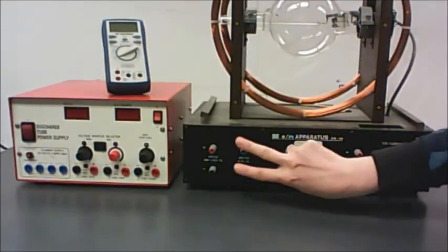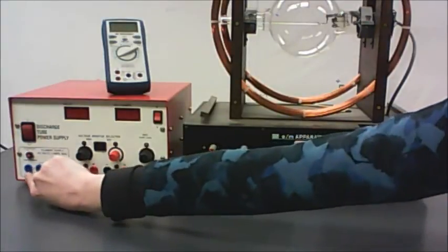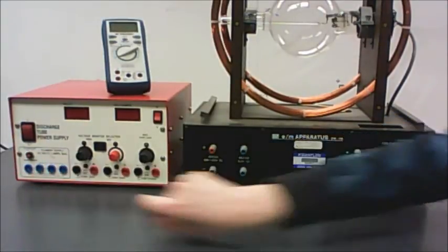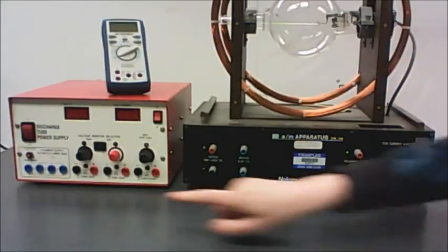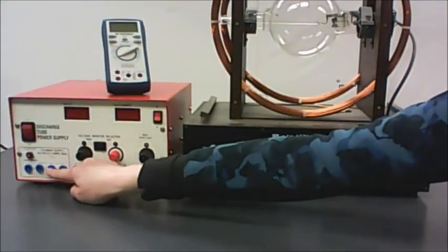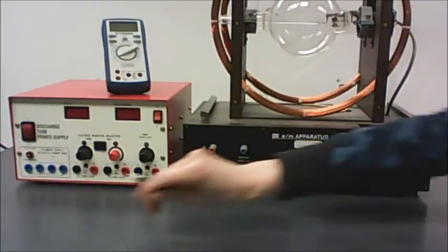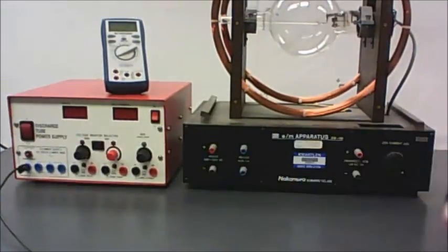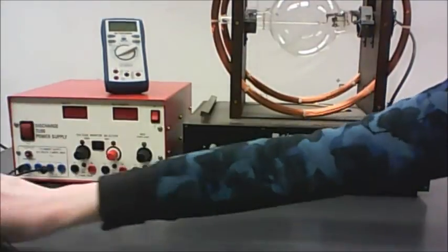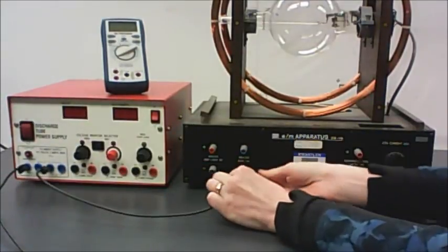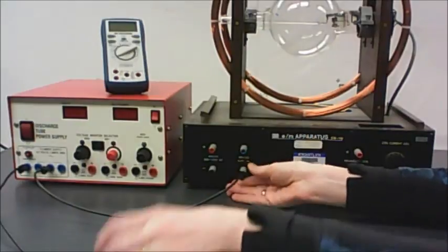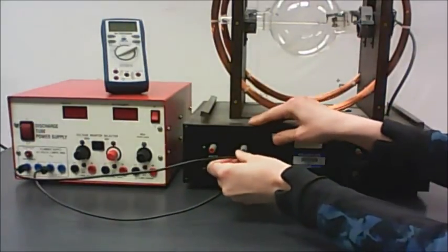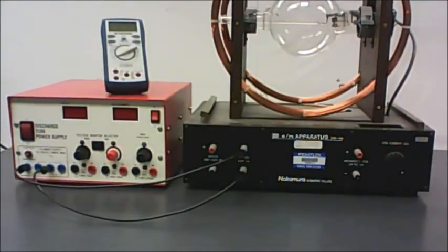These two terminals are going to be hooked up over here on the filament supply. If you look in your book, there is a little close-up that tells you you're going to plug into this one and this one. So you take your two cables, you plug one in here, and one in here, and then those get connected to the heater. This is an AC current, so it doesn't matter which terminal you hook up to which.